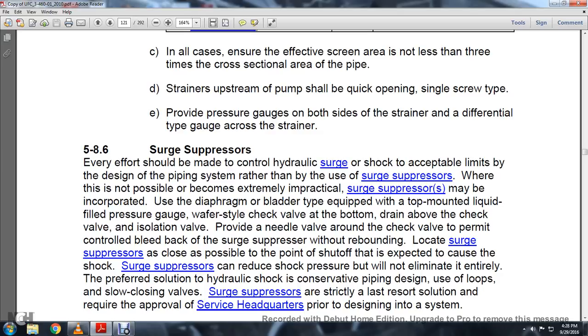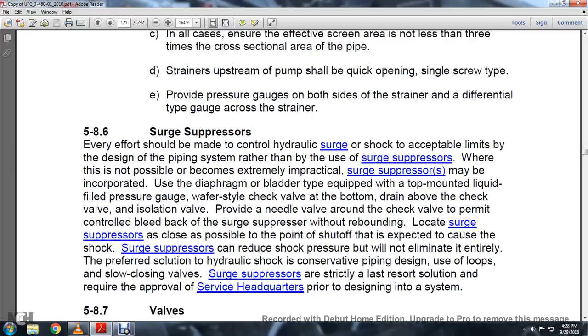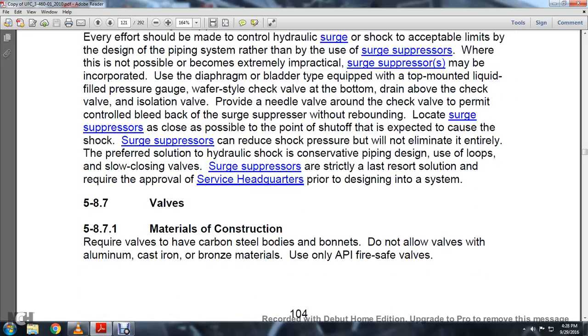Drain above the check valve and the isolation valve, and provide needle valves around the check valve to permit controlled bleed-back of the surge suppressor without rebounding. Locate the surge suppressor as close as possible to the point of shutoff that is expected to cause the shock. Surge suppressors can reduce shock pressure but will not eliminate it entirely. The preferred solution to hydraulic shock is conservative pipe design using loops and slow closing valves. Surge suppressors are strictly a last resort solution and require approval of service headquarters prior to design into a system.